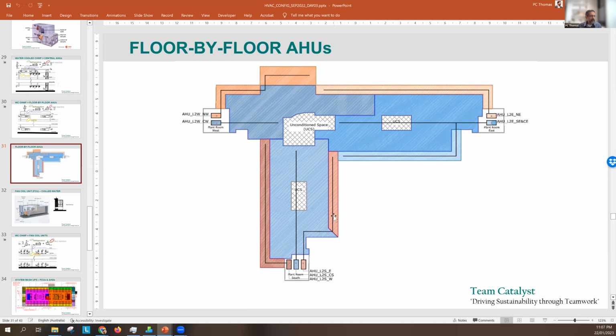Here's a perimeter zone, here's an internal zone. That kind of decision has to be taken finally by the air conditioning engineer, but the architect is able to just draw this. I guess it was mentioned as 12 to 15 feet, which is approximately 4 meters. We usually look at 3.6 to 4 meters. Air conditioning engineers will look for that as being a perimeter zone.